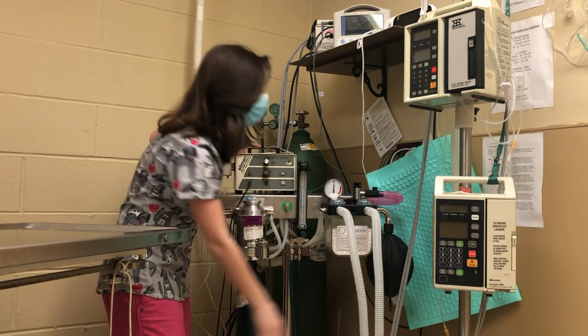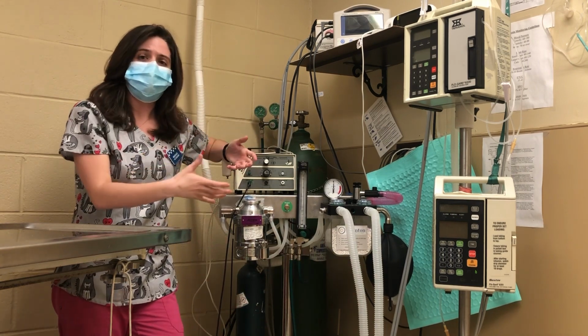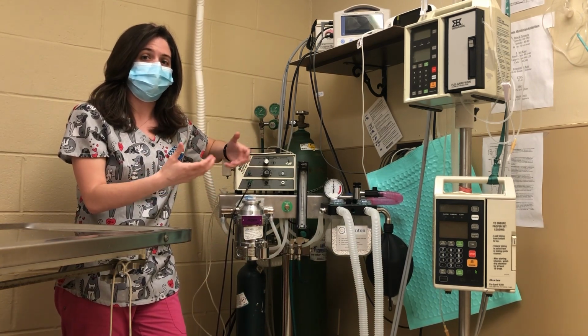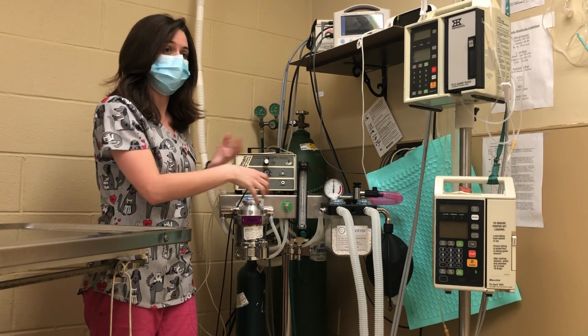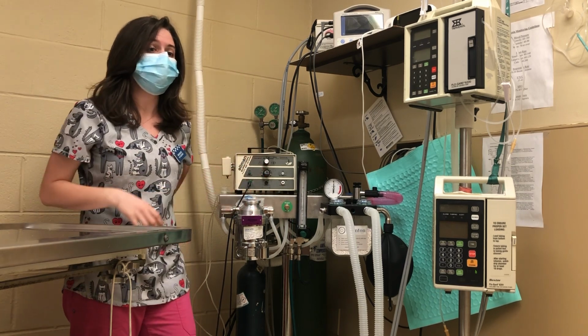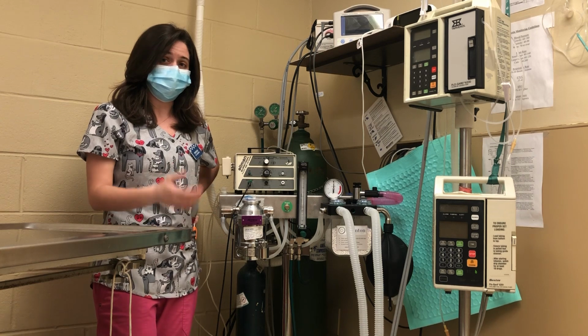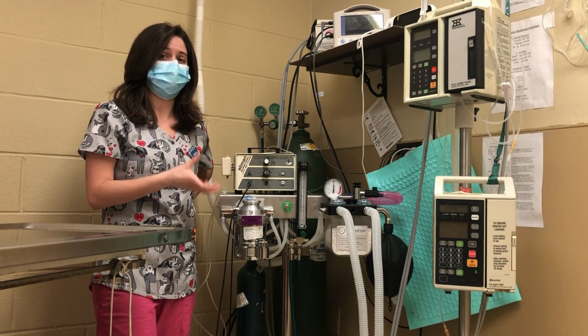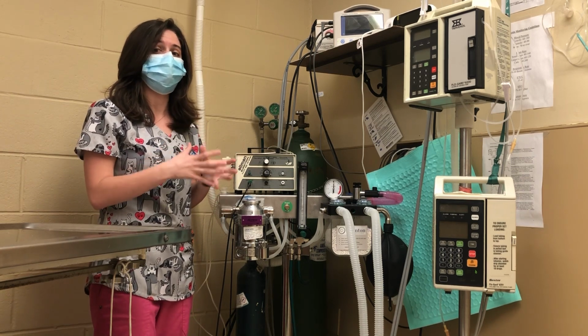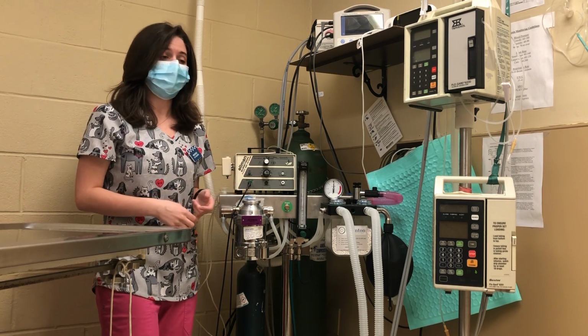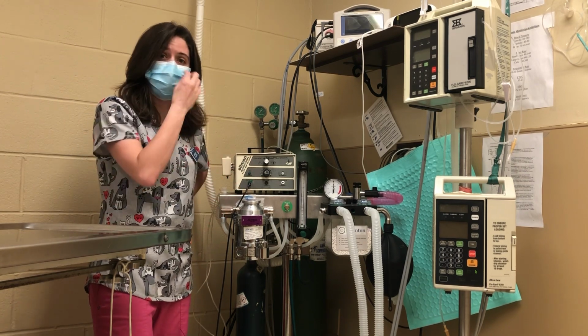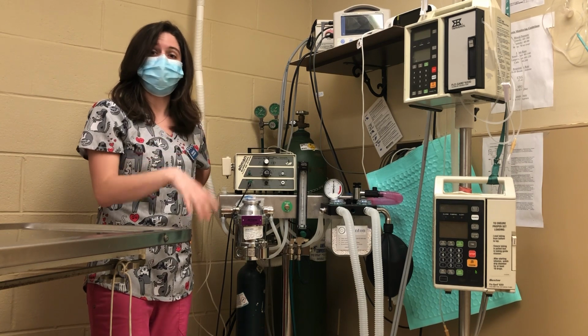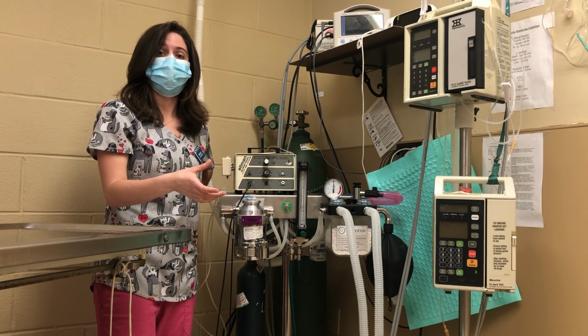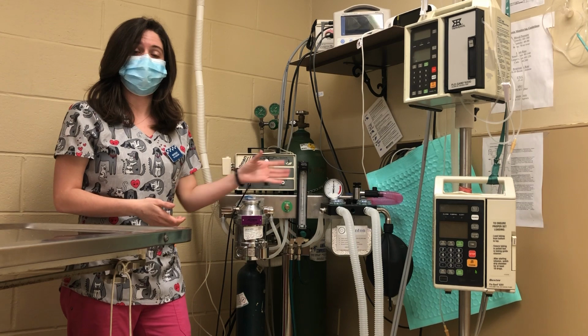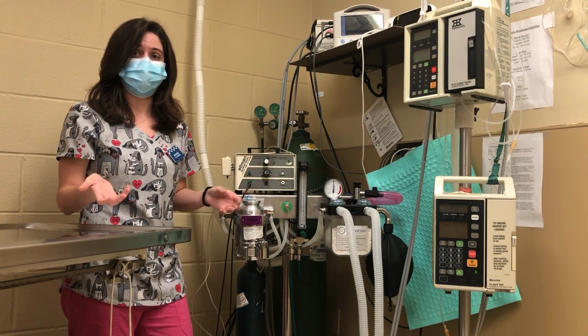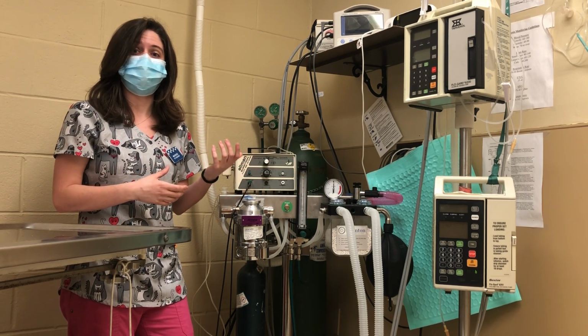Our reservoir bag. As the name suggests, it's a reservoir for air, so there's constantly going to be air hanging out in there just in case it's needed. And it's also a good indicator to a technician of how the patient's respiration is going, because it'll inflate and deflate as the patient is breathing. It's also helpful when you are inflating and deflating the ET tube cuff. You want to be able to give breaths so that you can hear if there's any leaking of the cuff.